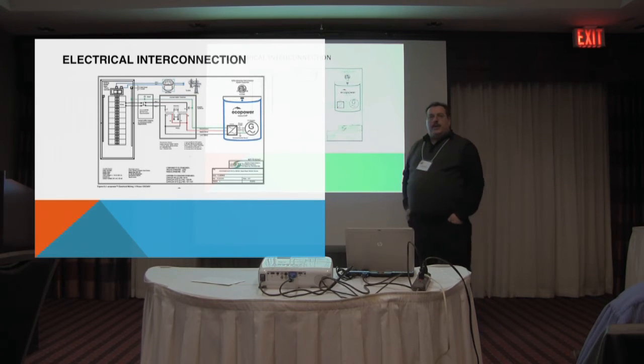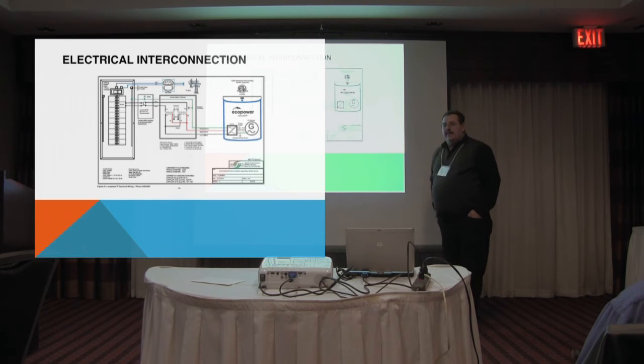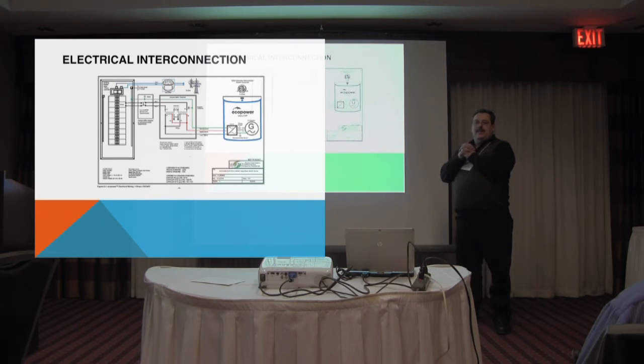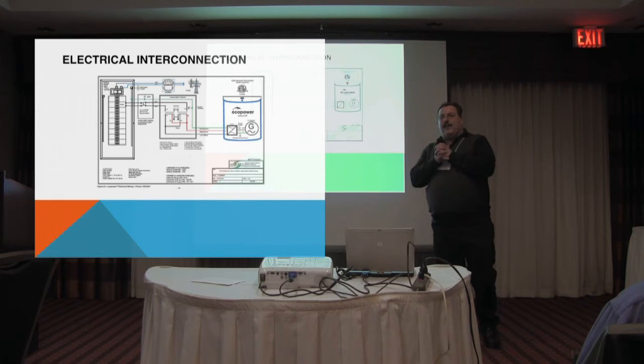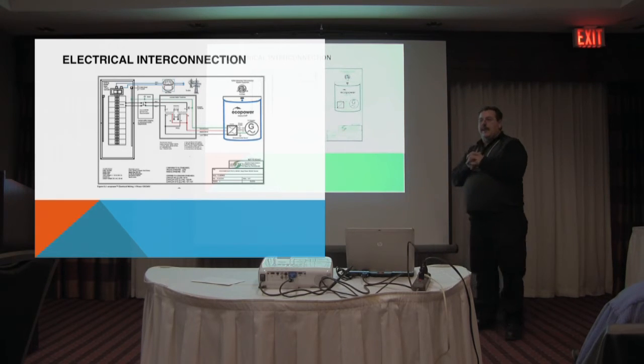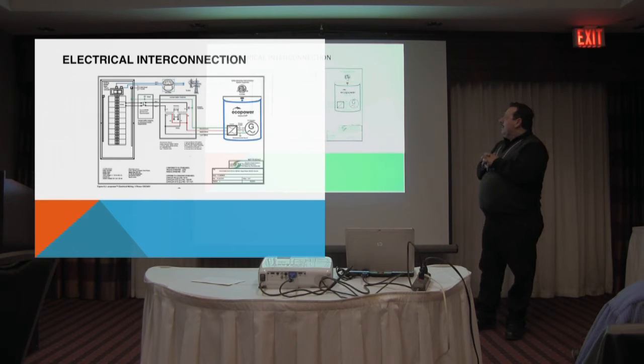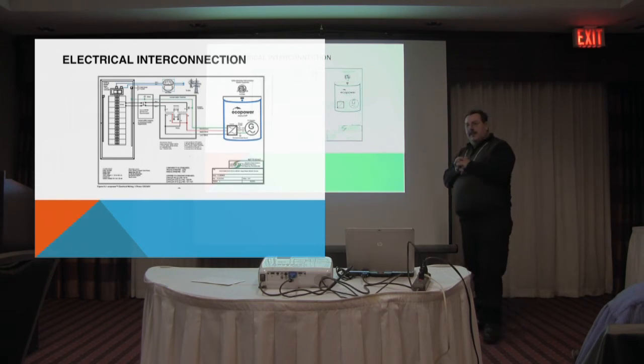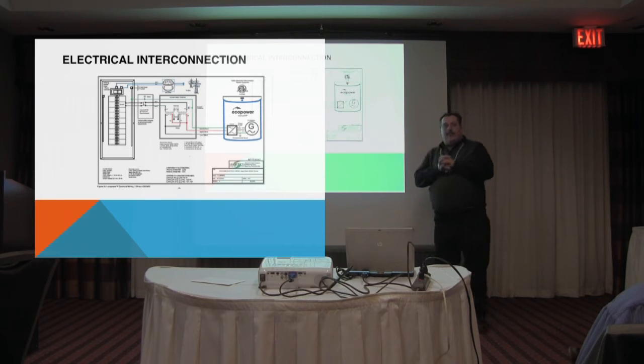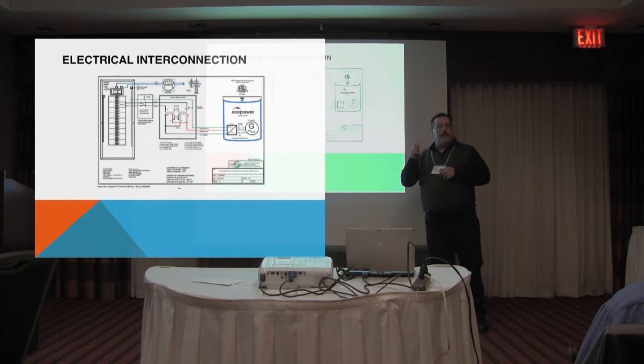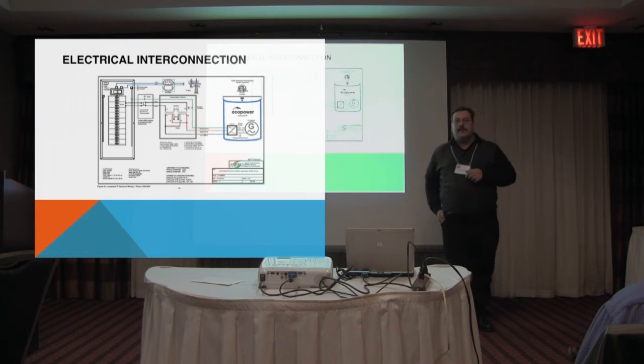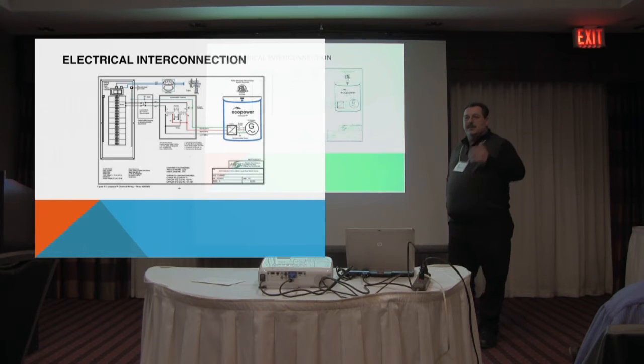These systems are grid dependent, and this is one of the things that I get asked all the time. When we get a power outage, can I run this unit? And the answer is no. It's not there as a backup generator. It's there to produce some energy and save you some money. So it is grid dependent. To meet all of the CSA requirements, it has to drop out within, I can't remember exactly the number of milliseconds, but if the power drops out, this unit has to drop out very, very rapidly. That's to protect the linesmen, so that we're not feeding power back while they're working on the power lines and not expecting that power there, and all of a sudden they're getting electrocuted.